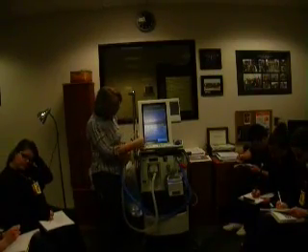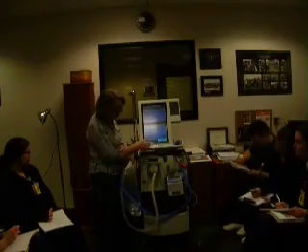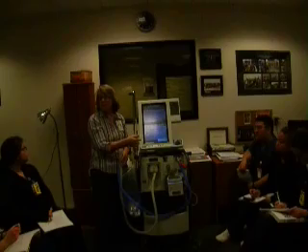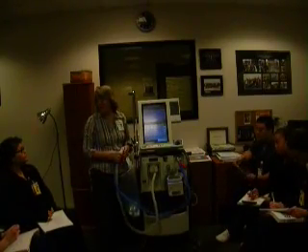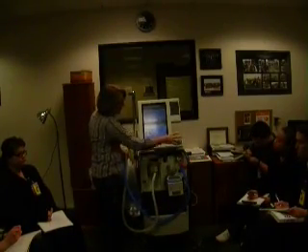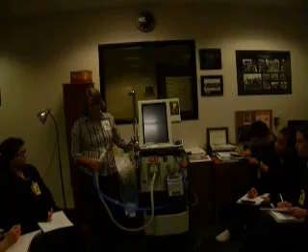SST testing completed. Normally, we wouldn't have to override. I have to override because we don't have oxygen. But normally, once this was done, you would say exit SST and it would restart on its own. If I exit SST now, because it hasn't passed, it's going to loop me right back into another SST, and it won't let me do anything. So we're just going to override it for now. Press accept. So the vent is going to shut down and restart on its own. It's part of this process, so that's normal.